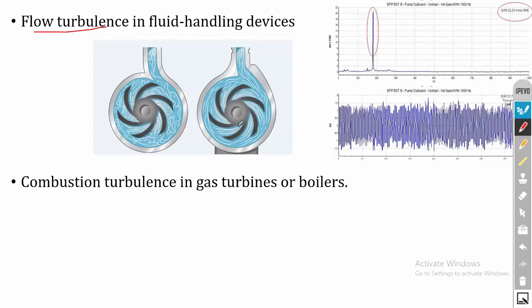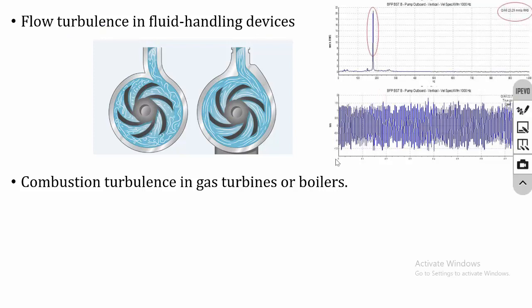This is the time domain signal for a turbulent pump — the amplitudes are high. If you convert this time domain signal into a frequency domain signal using fast Fourier transform, where the x-axis is time and y-axis is amplitude in the time domain, you can see a tall peak in the frequency domain because of the flow turbulence. The last internal force is combustion turbulence in gas turbines or boilers. During combustion, turbulence takes place and vibrates the gas turbine or boiler. These are all the internal forces that generate vibration.